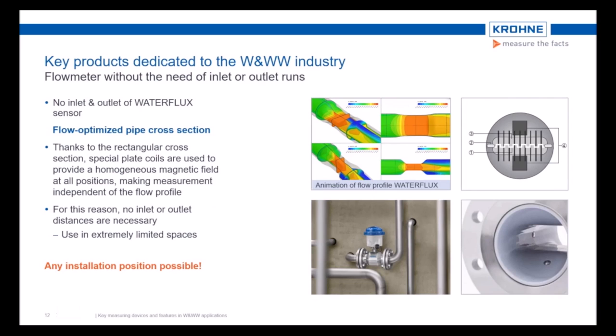How can we achieve this unique feature, no inlet and no outlet sections? Well, the flow meter water flux is built to have a flow optimized pipe construction, what you can see on the right hand side picture. Thanks to the rectangular cross section, special plate coils are used, what you can see on the picture above, which provide a homogeneous magnetic field at all positions, even at the edges, making measurement independent of the flow profile.